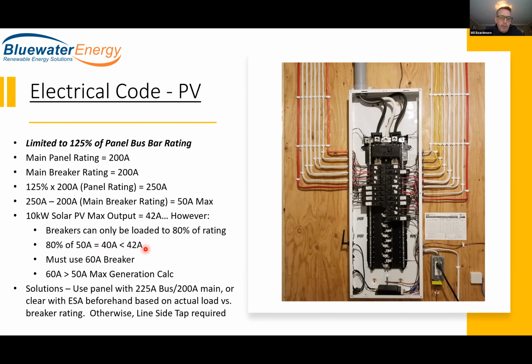So our 42 amp output from the inverter is actually greater than that. So we actually have to go to the next size up, which is a 60 amp breaker. Because the 60 amp breaker is greater than the 50 amp maximum remaining capacity that we can backfeed on that panel, we can no longer connect that solar array to the panel the way we used to. So a couple of things have to happen here.